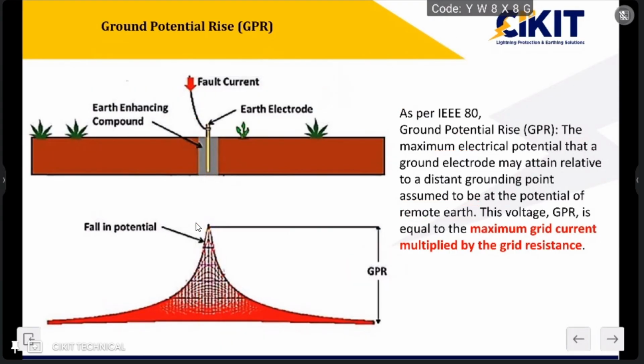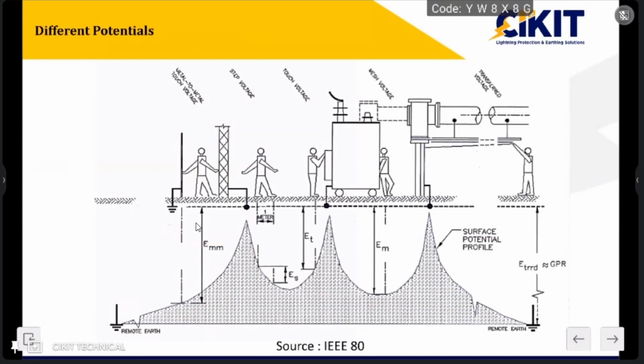That huge difference in the potential will be considered ground potential rise. The potential is nothing but the voltage. So the voltage will be equal to the grid current multiplied by the grid resistance, so V is equal to I into R. The same is applicable here. Here I is the grid current, whereas R is the grid resistance. By using this formula, we can calculate the value of ground potential rise.